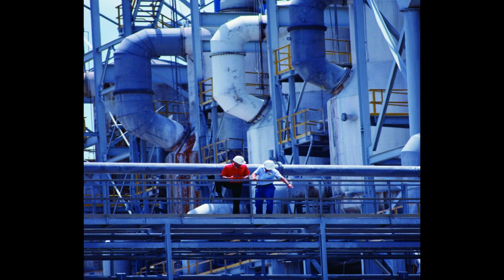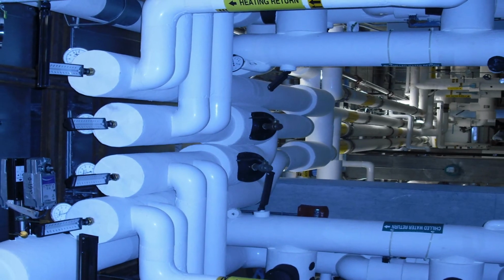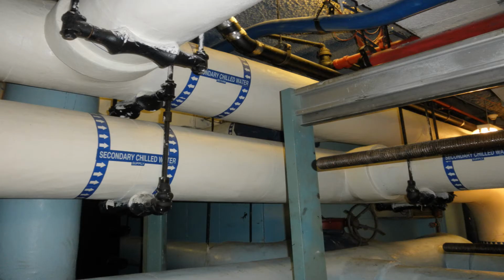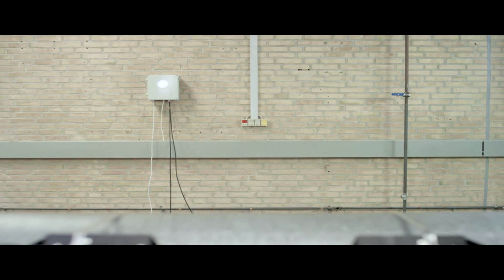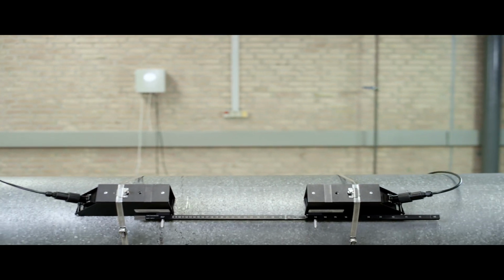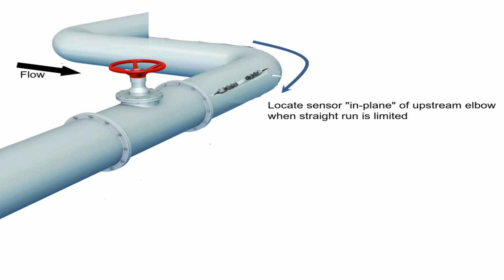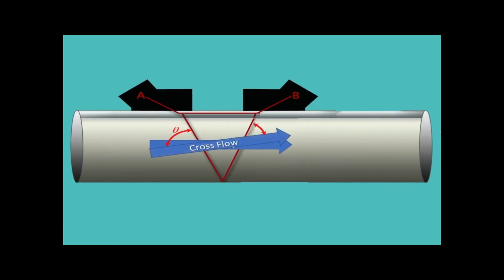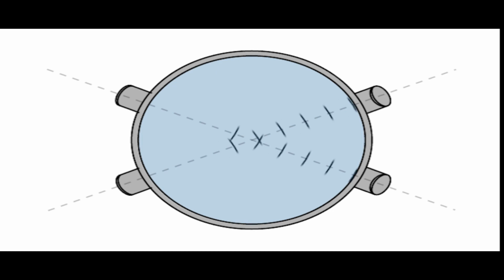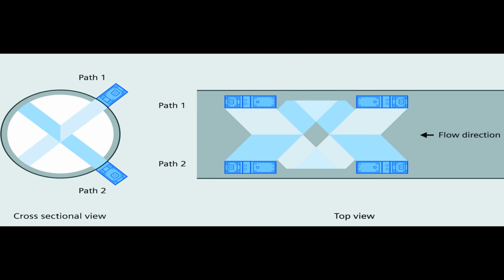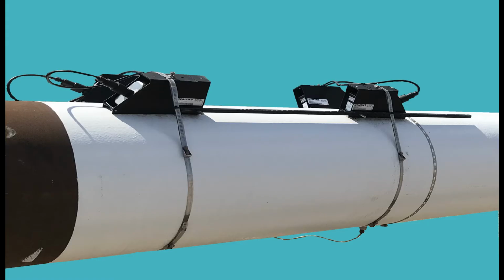First, look over your piping layout to see if there is a more suitable location than the one you first chose. One with more straight run or less anomalies on the upstream side. Second, mount your flow sensors in reflect mode, preferably in the plane of the elbow. This will negate crossflow errors because the sonic beam will pass through the flow stream at opposing angles, canceling the error produced by the non-axial flow angle. Third, further improvement of the flow profile averaging can be achieved using dual path measurement, where two pairs of sensors are installed 90 degrees apart for greater averaging of the cross-section of the pipe.